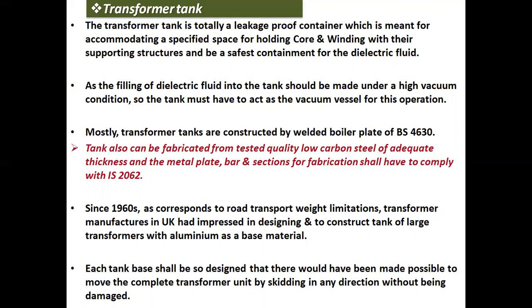Mostly, transformer tanks are constructed from welded boiler plate of BS 4630. The tank can also be fabricated from tested quality low carbon steel of adequate thickness, and the metal plate and bar sections for fabrication shall comply with IS 2062. In the 1960s, corresponding to road transport weight limitations, transformer manufacturers in the UK were impressed into designing and constructing tanks of large transformers with aluminum as the base material.